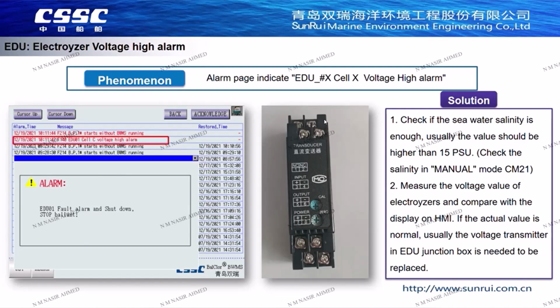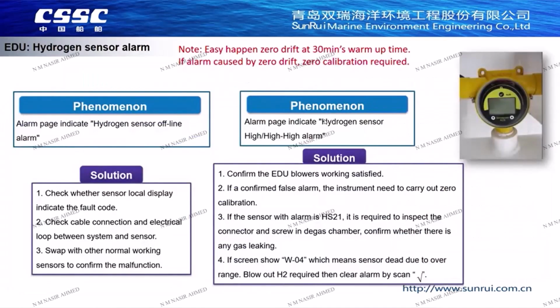Secondly, the actual voltage at both ends of the electrolytic cell can be measured with a multimeter to confirm whether it is a fault of the voltage transmitter. The transmitter can be found in the EDU junction box. If direct measurement is dangerous, you may directly interchange the faulty transmitter with another normal one to confirm the transmitter malfunction itself. Next one is the hydrogen sensor.